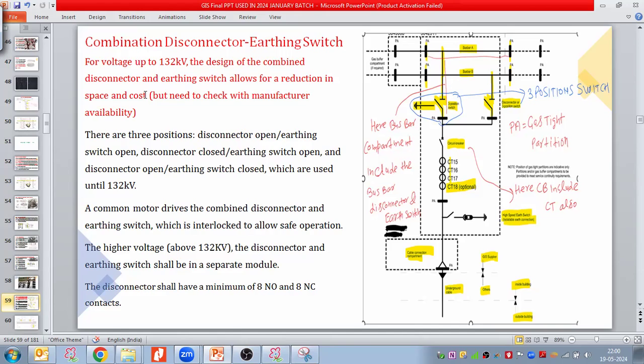But we have to check with each manufacturer whether they have it at that particular voltage, for the project voltage level you are working at, and whether the manufacturer from where you are taking the GIS has this combined assembly or not. I am putting this statement here because it is not possible that each and every manufacturer has this arrangement. Generally most manufacturers do, but we need to check. Generally, up to 132 kV, we take this combined arrangement.